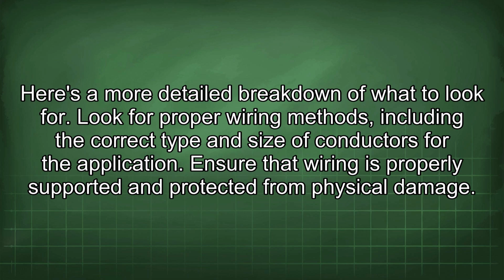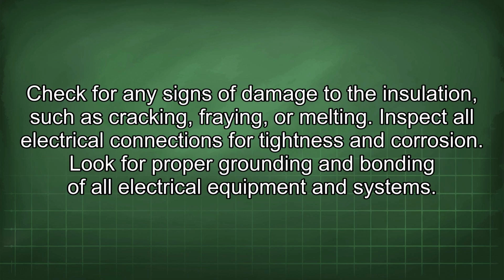Look for proper wiring methods, including the correct type and size of conductors for the application. Ensure that wiring is properly supported and protected from physical damage. Check for any signs of damage to the insulation, such as cracking, fraying, or melting. Inspect all electrical connections for tightness and corrosion.